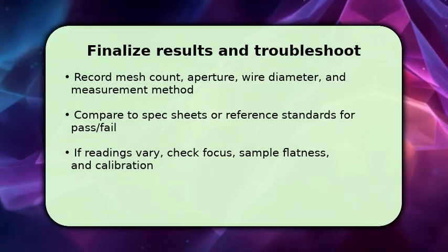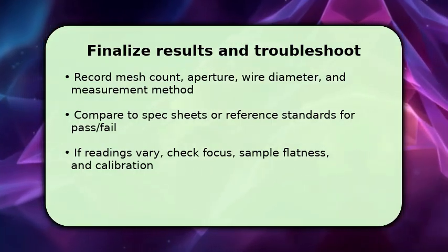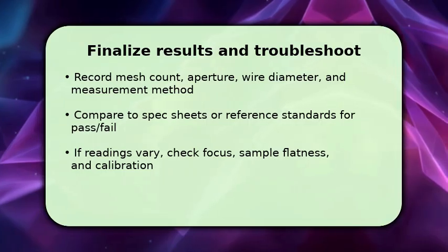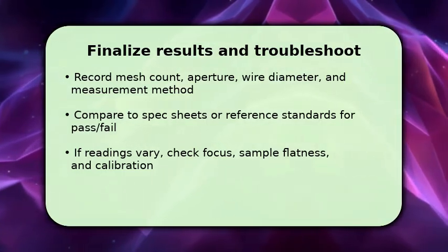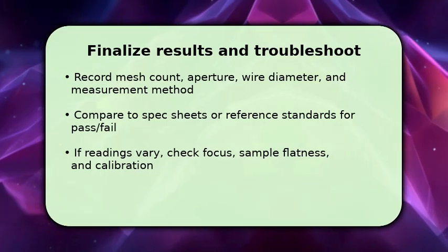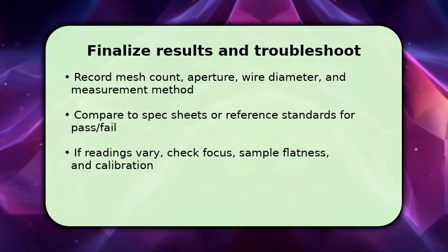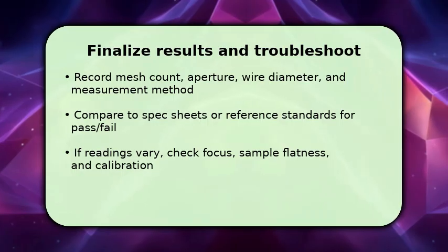If results seem inconsistent, troubleshoot. Make sure the optics are calibrated, the sample lies perfectly flat, and lighting doesn't cast shadows. A single tip: if readings vary widely, re-clean the mesh and remeasure at more locations until values converge.